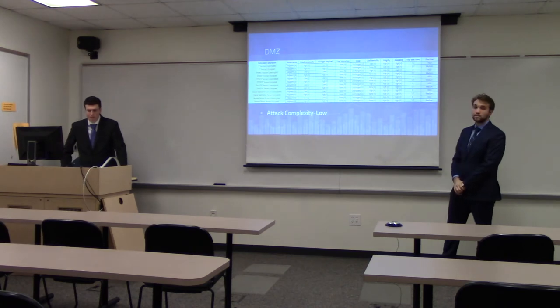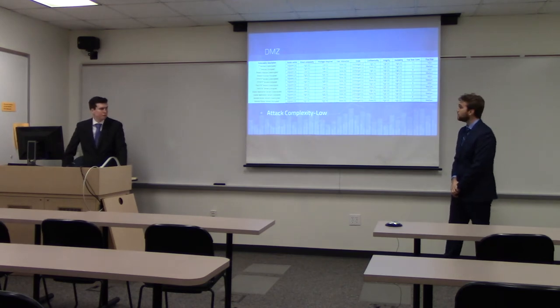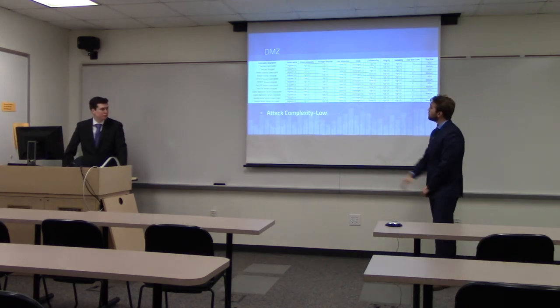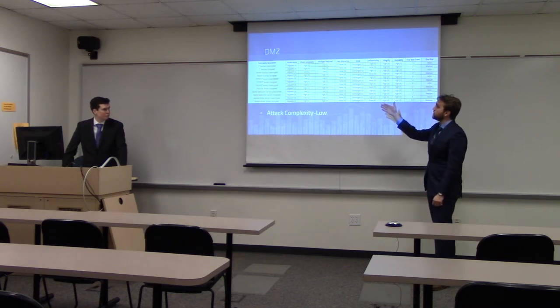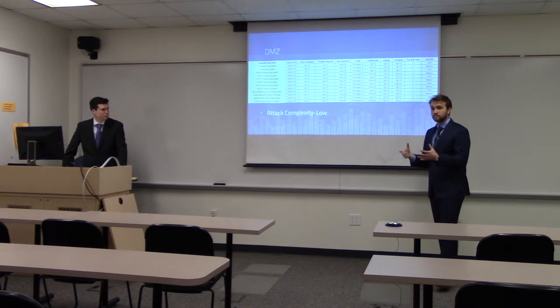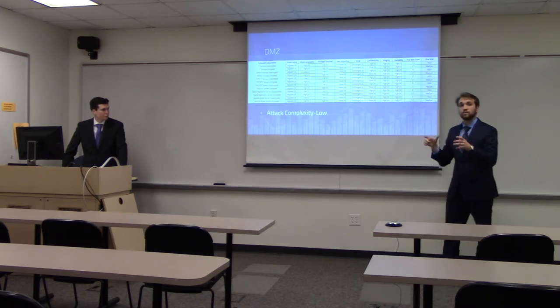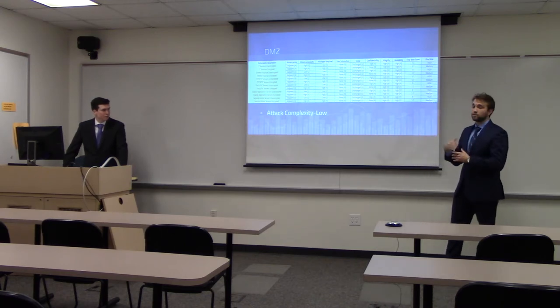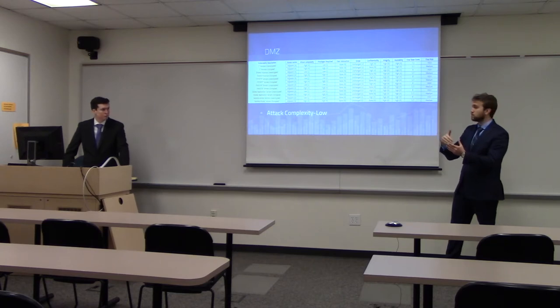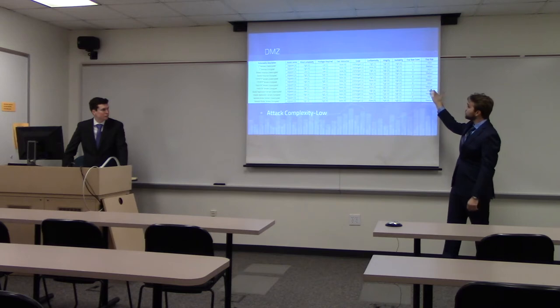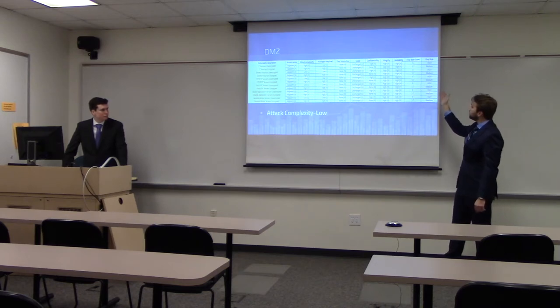This is the DMZ, or demilitarized zone. At this level, attack complexity is now low on some data streams because the DMZ is higher up in the Purdue model, meaning an attack would need to pass through fewer firewalls to access these data streams. This results in a higher final base score for unencrypted systems — up to 8 — while encrypted systems remain at 5.7, which is medium.